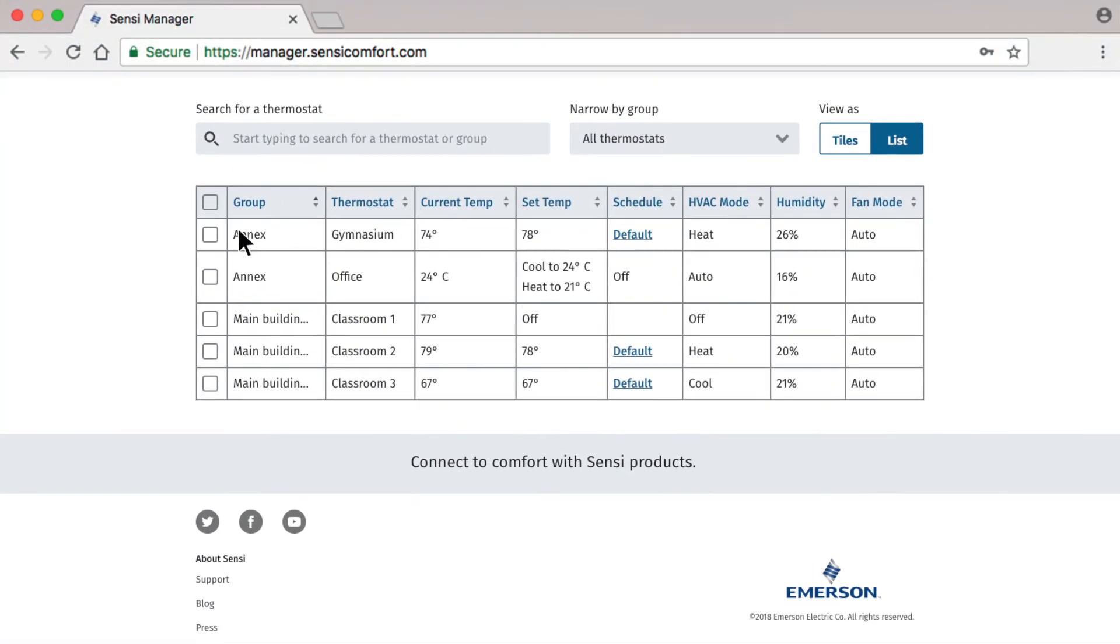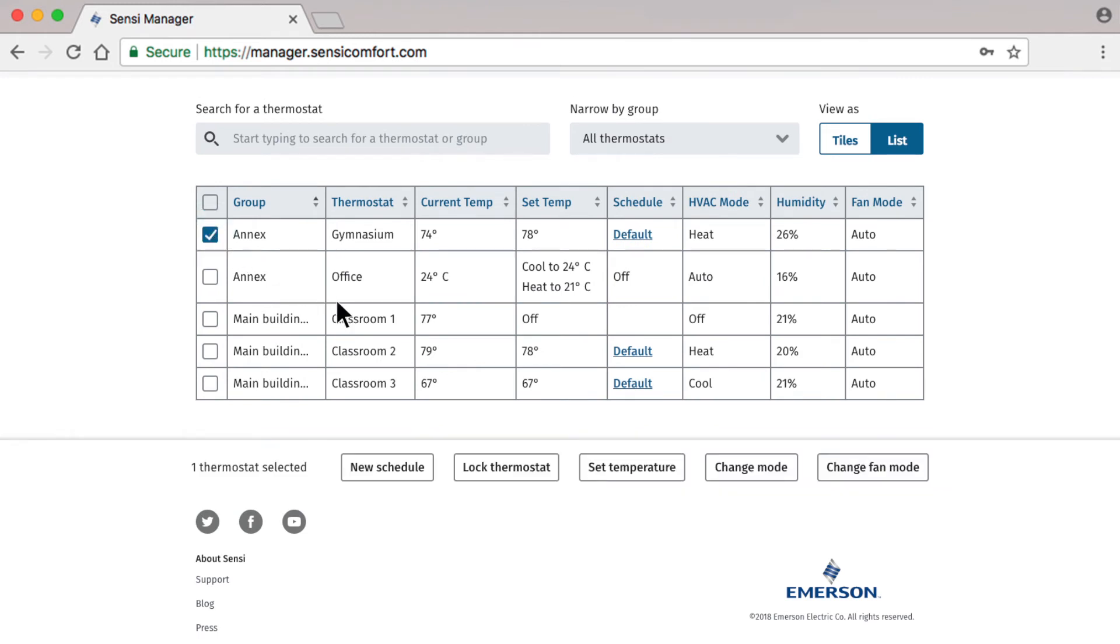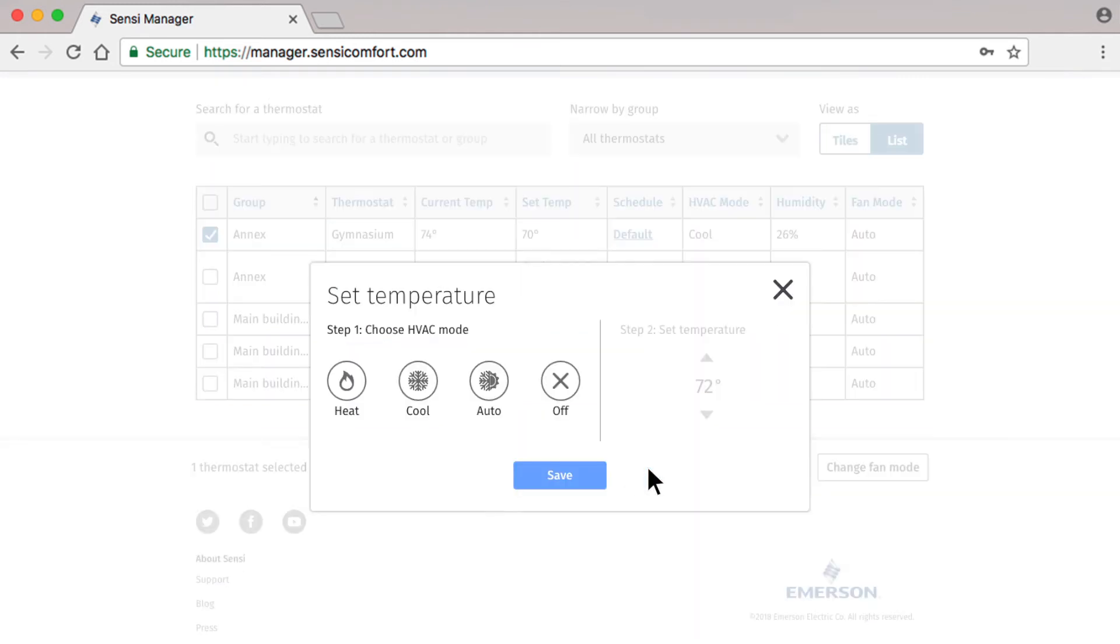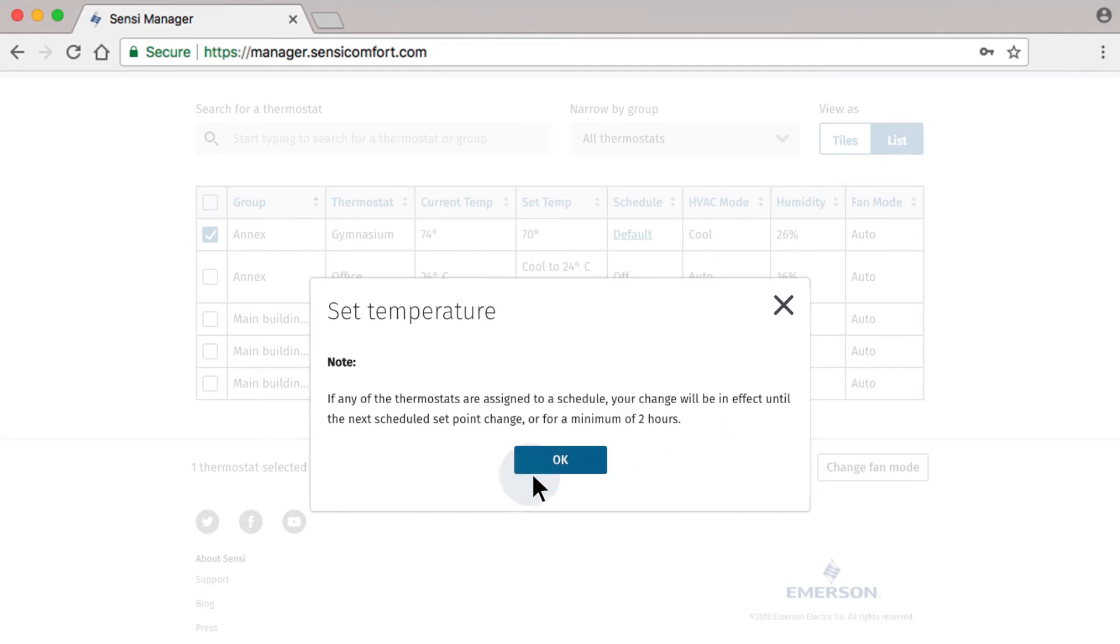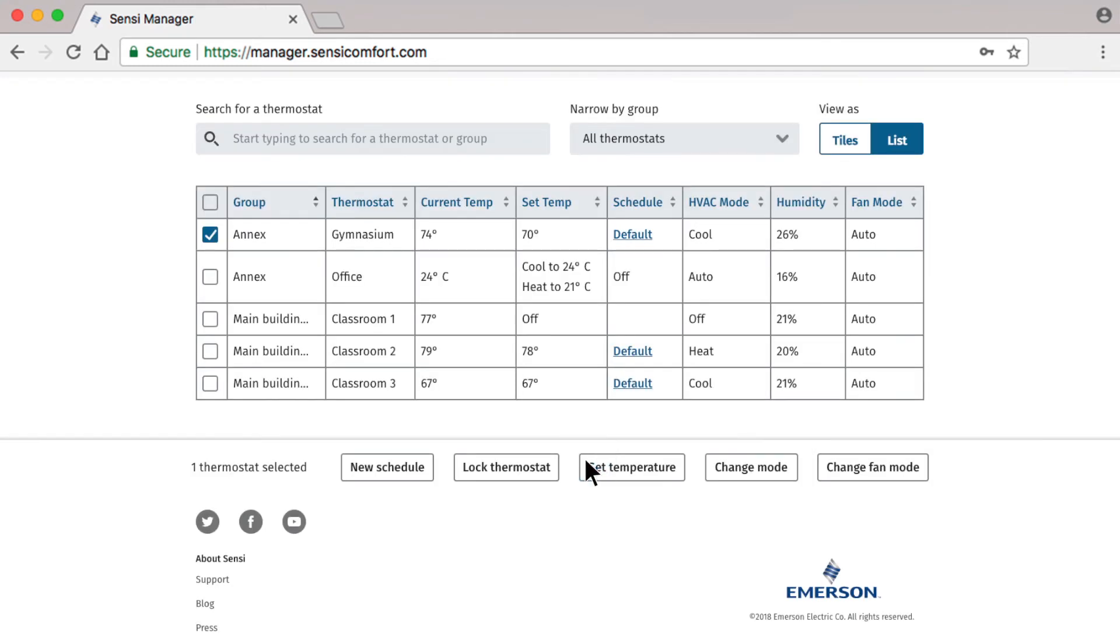Check Gymnasium, then select Set Temperature, check your preferred mode, and bring the temperature down. You will get a message notifying you that if this thermostat is on a schedule, these actions will be a temporary override. This is helpful to accommodate current activities in the gym, while allowing the thermostat to automatically return back to its regular schedule later.